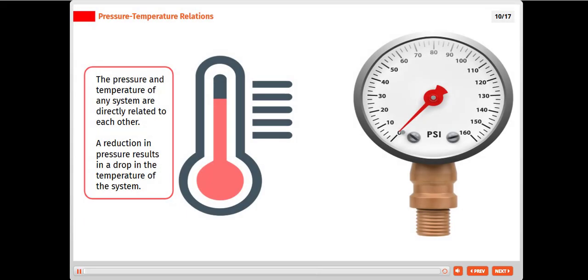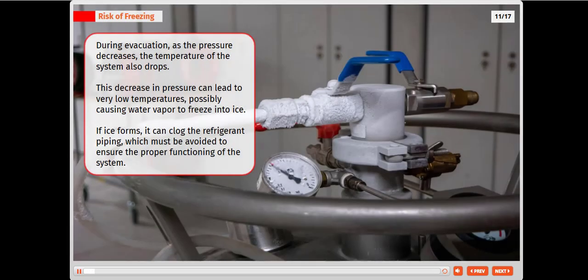The pressure and temperature of any system are directly related to each other. A reduction in pressure results in a drop in the temperature of the system. During evacuation, as the pressure decreases, the temperature of the system also drops. This decrease in pressure can lead to very low temperatures, possibly causing water vapor to freeze into ice. If ice forms, it can clog the refrigerant piping, which must be avoided to ensure the proper functioning of the system.